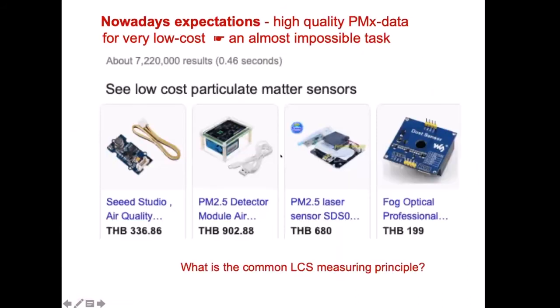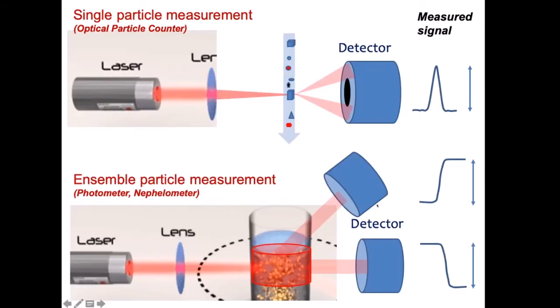The other sort of measurement is the situation where we have a lot of particles passing through the beam of light. Either the detector can be looking into the laser, which is rather rare—we would then have a weakening of the signal because of the presence of particles—or when the detector is off the line from the laser, we would have an increased signal coming from the presence of the particles.